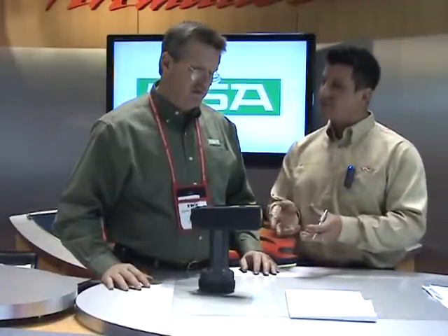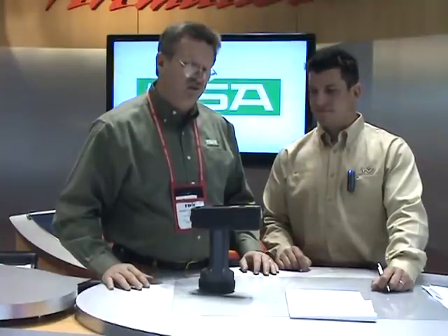Let's talk a little bit about the technology that's in it. MSA has been probably developing a unit like this for a long time now, correct? This product actually came from an acquisition MSA made several years ago from Microsensor, a Kentucky company. The technology used is called SAW technology, which stands for Surface Acoustic Wave. The simplest way to describe it — it's like taking a fingerprint, a chemical fingerprint. It analyzes it, and if it's positive you'll get an indication on the screen; if it's negative, no alarm will go off.